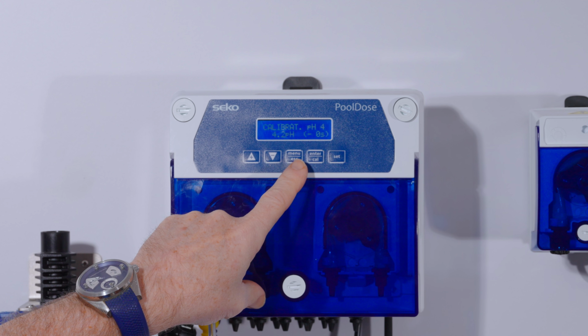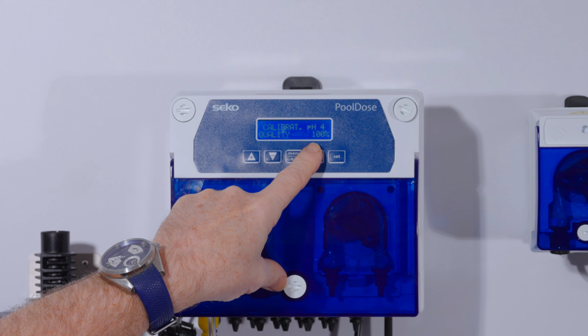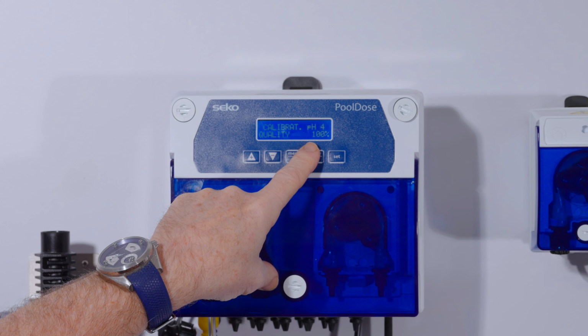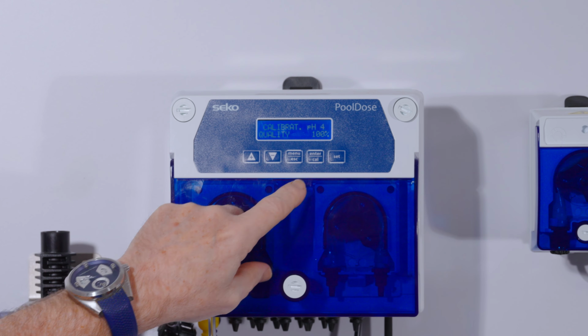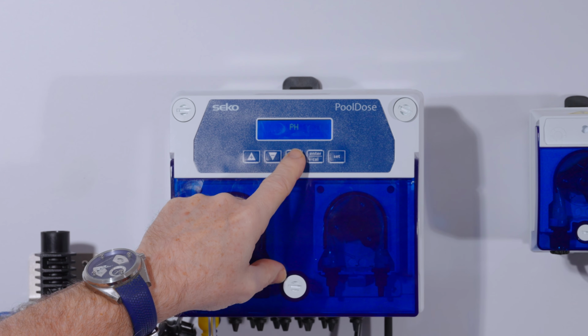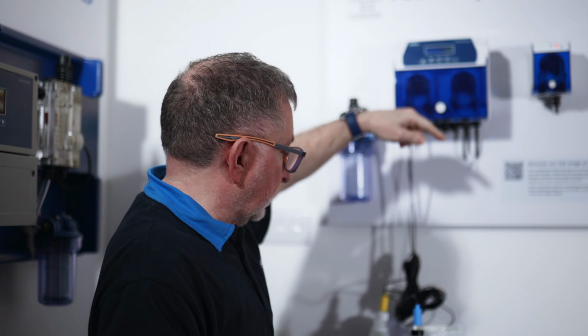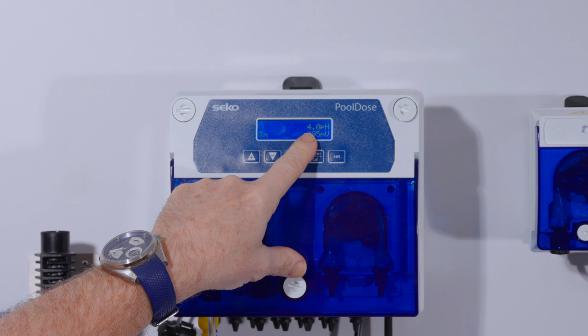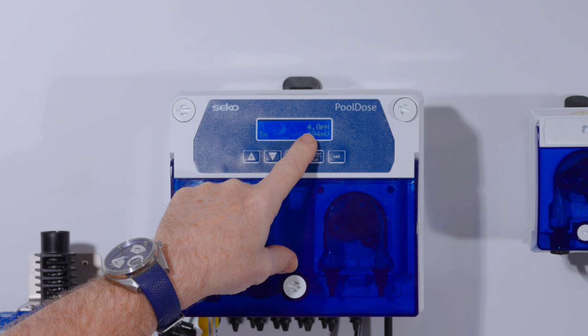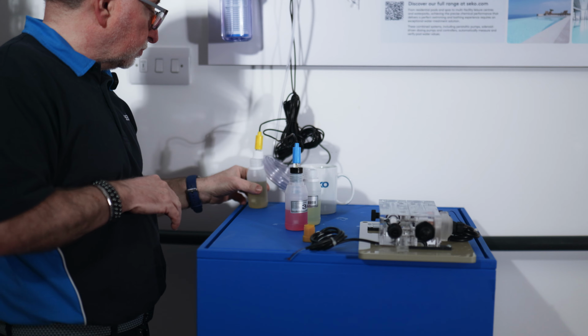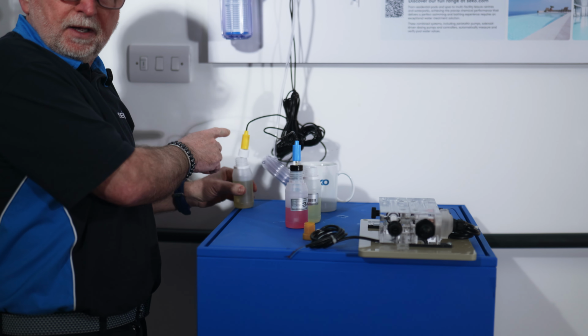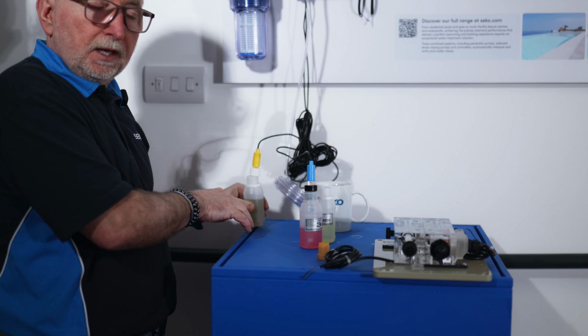So we've now finished the countdown, and once again the quality of the probe in this solution has come back at 100% and the calibration is complete. If we press enter, we can go back to the menu and escape back out. You can see now that being in the 4 pH solution the reading on the screen is exactly 4 pH.